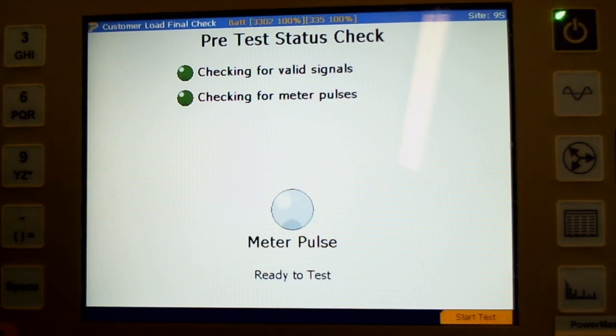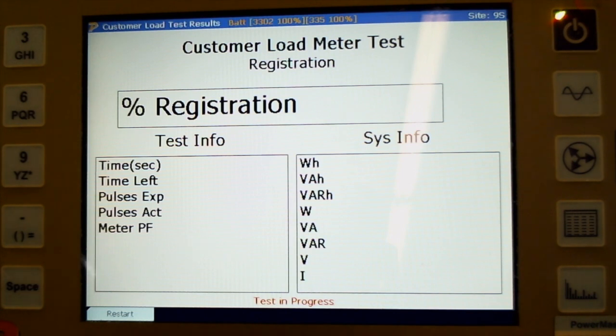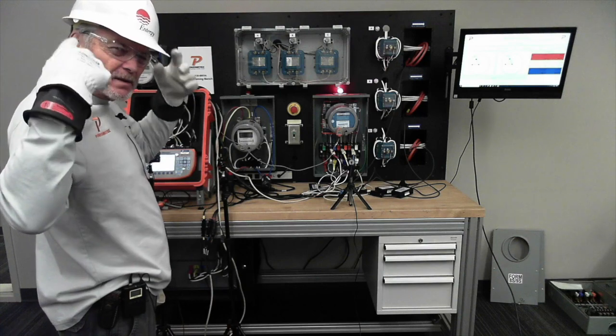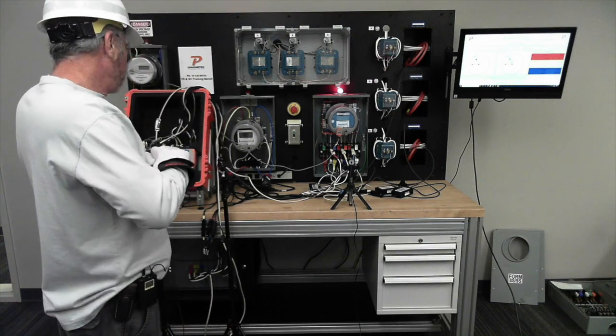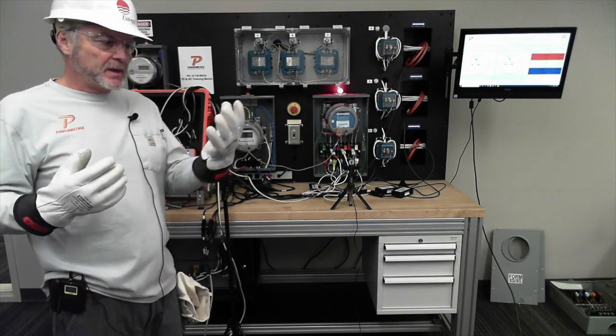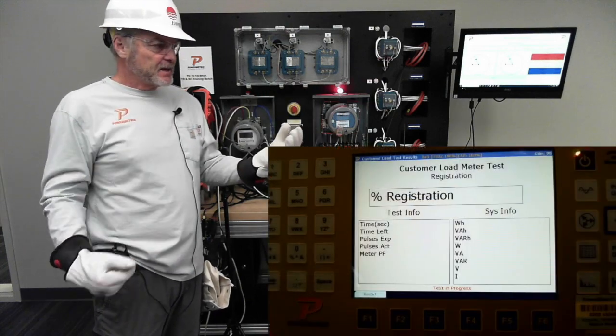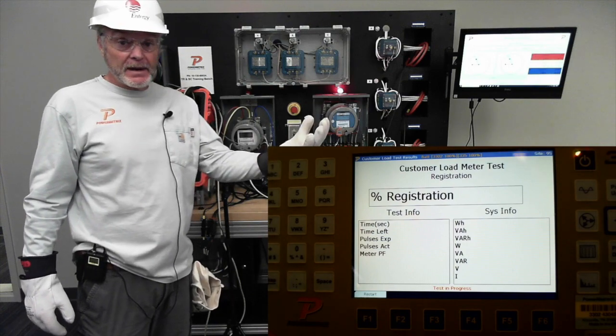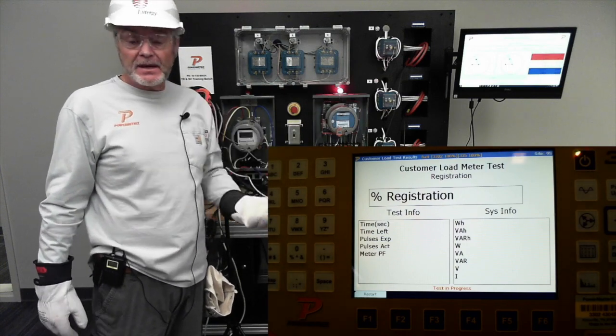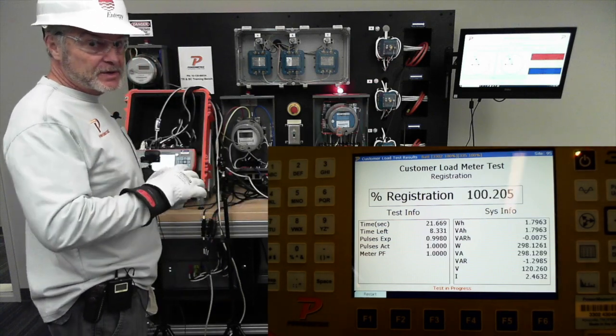Notice it took a little while. When you're out there, you're taking all these clues in, looking at everything, listening for humming noises. Because what happens is you get a loose connection over time, it gets loose, and starts rattling and vibrating. So you're listening, you're looking, melting all these clues together, and you go, okay, I think I know what the problem is now. That's why it's such a big deal to be able to tell whether the problem's on the primary side or the secondary side. Because when you finally say you think you've got a problem on the primary side, you're going to have to call in the bucket trucks, the linemen, and go up there and check everything. So you want to make sure you know what you're talking about before you do that.